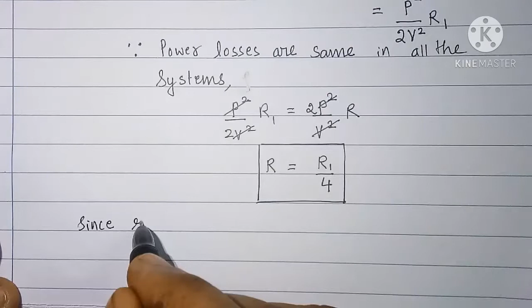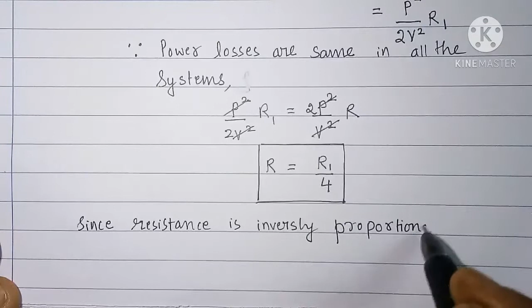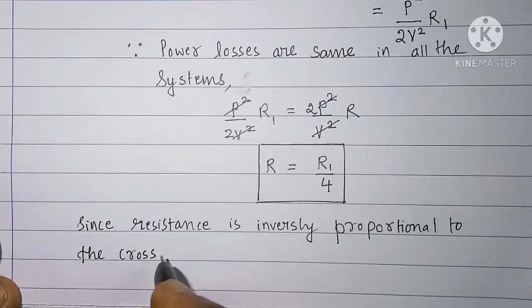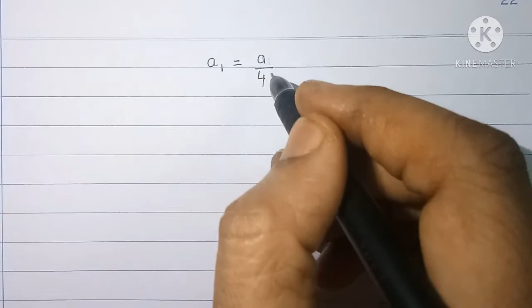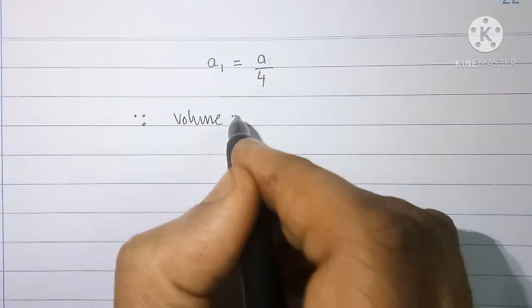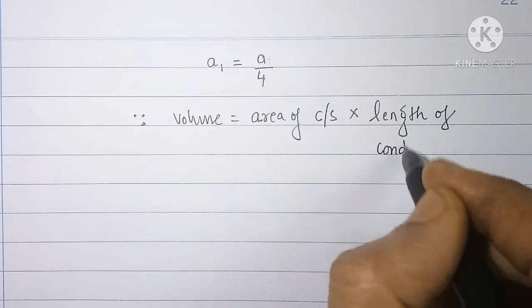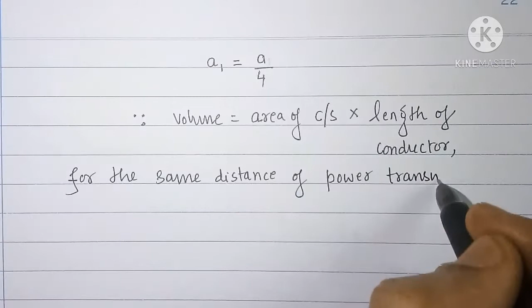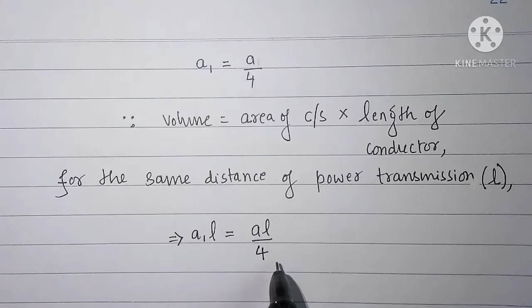Since resistance is inversely proportional to the cross-sectional area of conductor, the cross-sectional area of conductor A1 is equal to A by 4. Since volume is equal to area of cross section into length of conductor, for the same distance of power transmission, L unit length, we can write A1L is equal to AL by 4, or V1 by V is equal to 1 by 4, that is equal to A1 by A, where A1 into L is equal to V1 and A into L is equal to V. It means that the volume of the conductor used in DC two-wire system with midpoint earthed is equal to 1/4 the volume of conductor used in DC two-wire system.